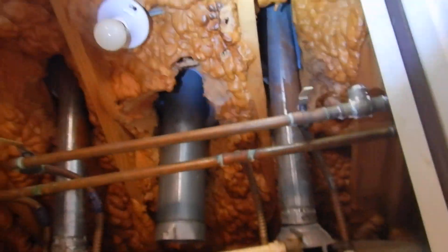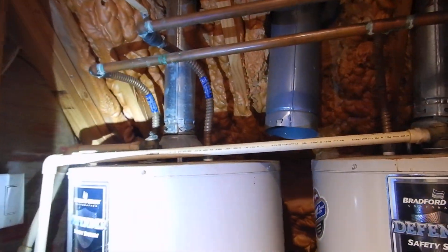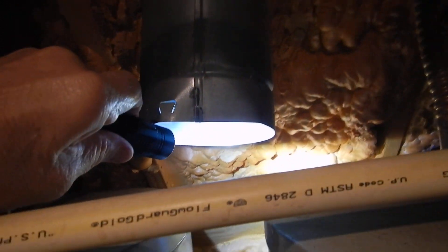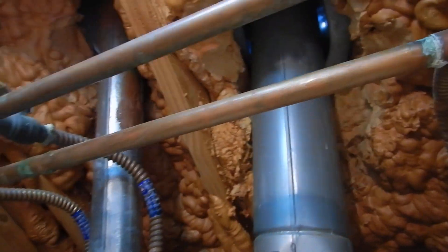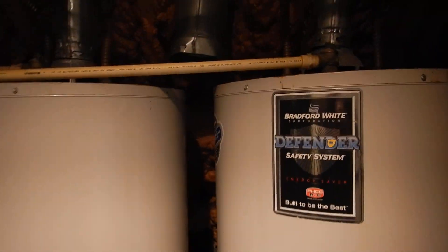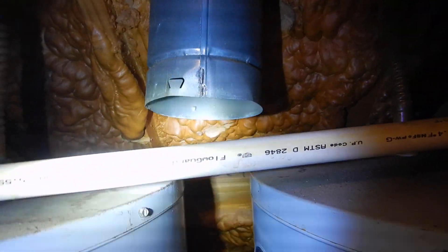When you have a spray foam attic it is encapsulated — no air gets in, no air gets out. Now we've compromised the insulation system by bringing a combustion air vent in here. This is supposed to be a sealed attic, a sealed water heater closet, but all these compromises in the seal, including by design, undermine that.